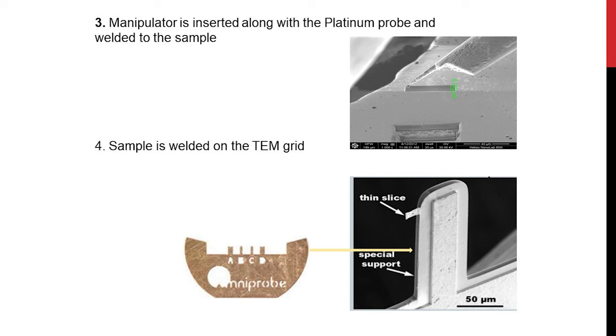The zoomed in image of one slot is given here. Once the thin slice is lifted off, we weld it on the grid. After welding, the thickness will be in the order of 1 micron, so we need to reduce the thickness to less than 100 nanometers with the help of the ion beam. Once you make the thin slice less than 100 nanometers, the same grid is taken for TEM analysis. This in-situ deposition, milling, and lift-off procedure is termed TEM lamella preparation.